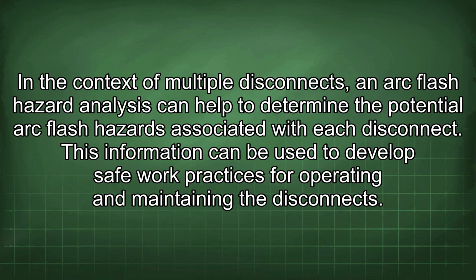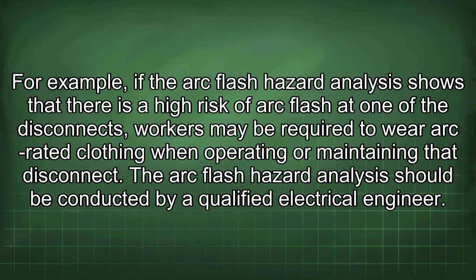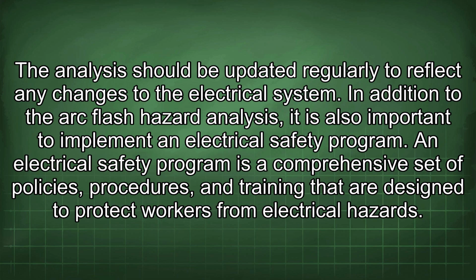In the context of multiple disconnects, an arc flash hazard analysis can help to determine the potential arc flash hazards associated with each disconnect. This information can be used to develop safe work practices for operating and maintaining the disconnects. For example, if the arc flash hazard analysis shows that there is a high risk of arc flash at one of the disconnects, workers may be required to wear arc-rated clothing when operating or maintaining the disconnect. The arc flash hazard analysis should be conducted by a qualified electrical engineer. The analysis should be updated regularly to reflect any changes to the electrical system.